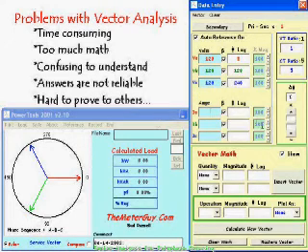Now, as soon as we enter a current for any of these, it's going to start calculating kW, kVA, kVAR, and power factor. Let's start the first one at 7 amps, and let's put it at 12 degrees. And it says that the kW is 0.82, 820 watts. You want to see that?